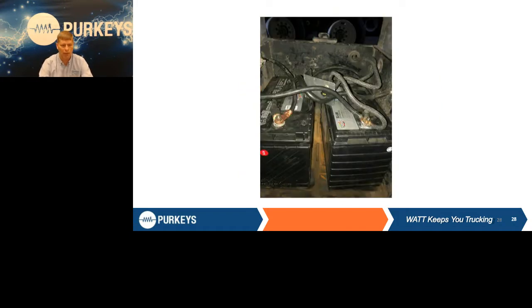Here's that same battery box I was talking about before, where the liftgate circuit breaker was bypassed. Well, our breaker for the charging system, somebody just left laying in the battery box. That is all bare aluminum and very easy for it to get over there and touch the positive on the battery over to the case of the liftgate battery box. So again, take a couple of minutes, make sure it's securely fastened. And if you notice something else, no hold down. So multiple things, still, we don't have time to fix it right, but we've got time to work on it 3 or 4 times.